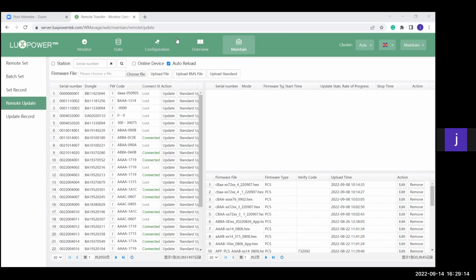Then, while I'm on the update, the last thing on the updates that's very important is the machine has to have Eskom power or PV power to update this unit. The unit's MPPT board is activated by Eskom or activated by PV power. And it has to have one of those to update. And it is very important.